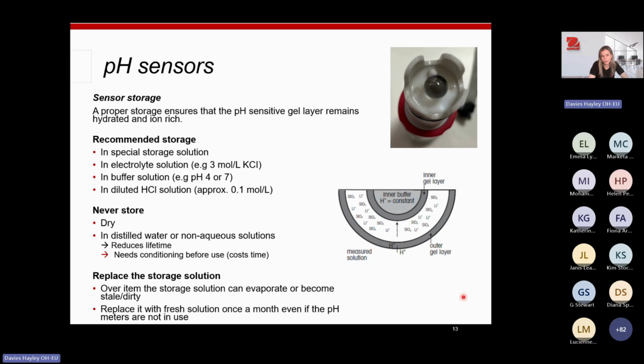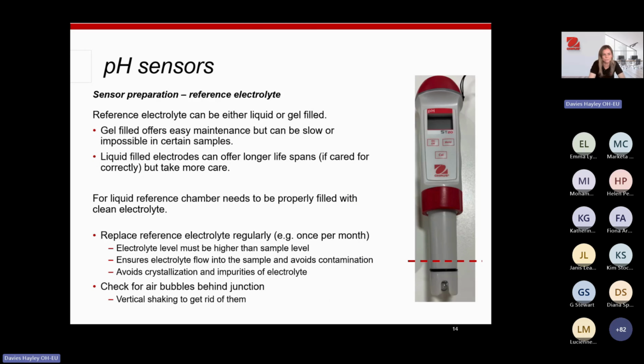Replace the storage solution. Over time the storage solution can evaporate, it can become stale, it can be dirty, it can get bacteria inside. So it is recommended to replace the storage solution once a month with fresh solution, even if the meters are not in use. It's always good practice not to top up. We would replace it: wash out the wetting cap, pop some fresh solution in, and do that once a month. This is all to get the best and the longest life out of your electrodes.